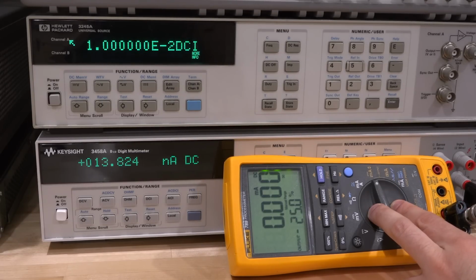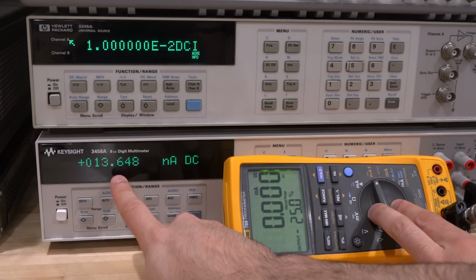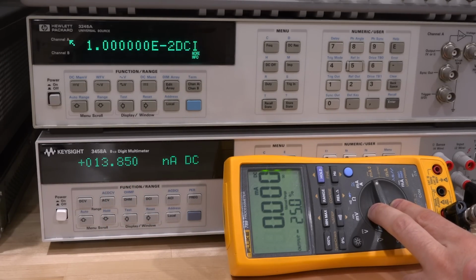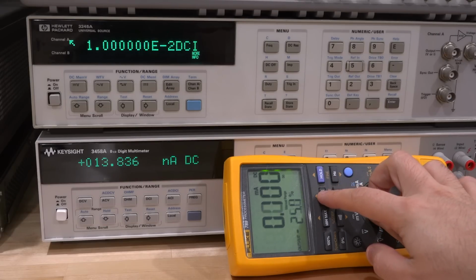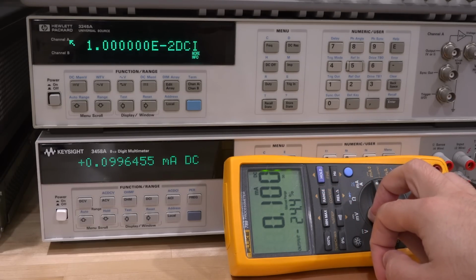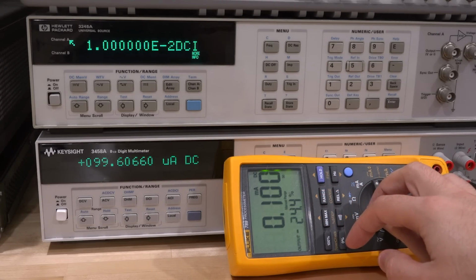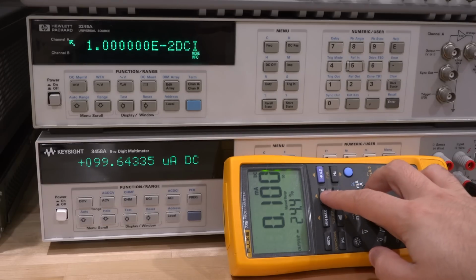So let's try the current source capability of this instrument, which is one of the features of the 789 process meter. So right now it's set to 0 milliamp, and you can see we're reading about 13 nanoamp here on the Keysight 3458A, so there's nothing there. Now you can go up to 100 microamp. Let's see what happens. And it's really close to 100 microamps, 99.6, pretty good.